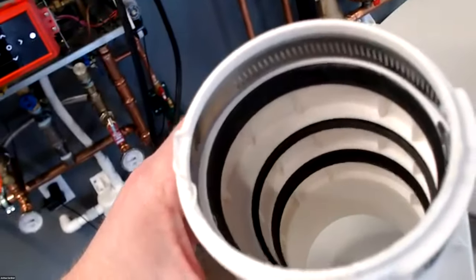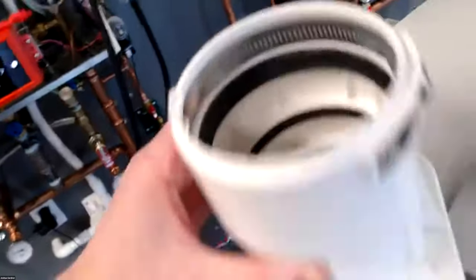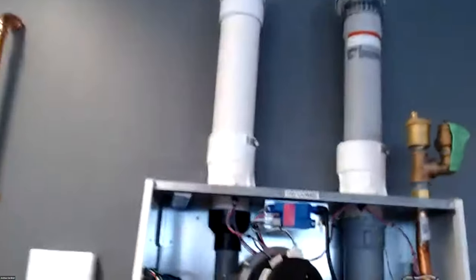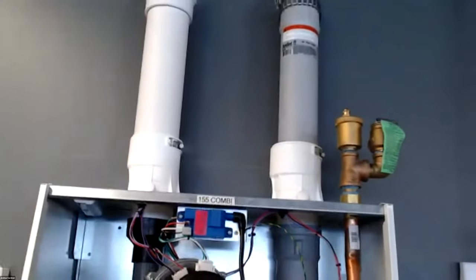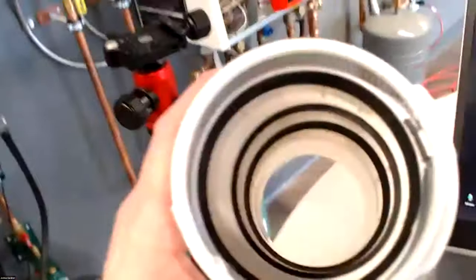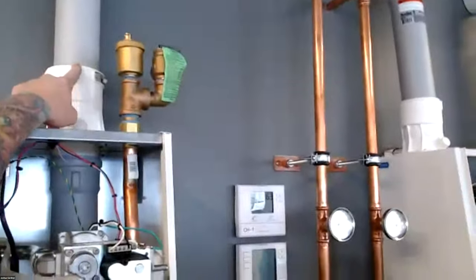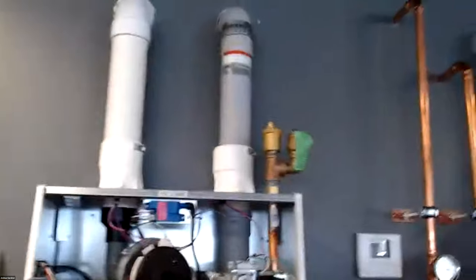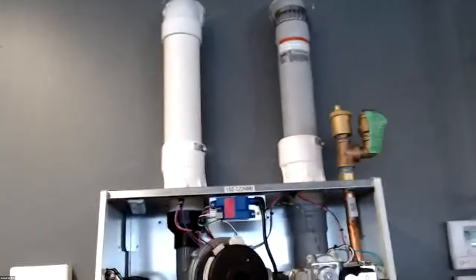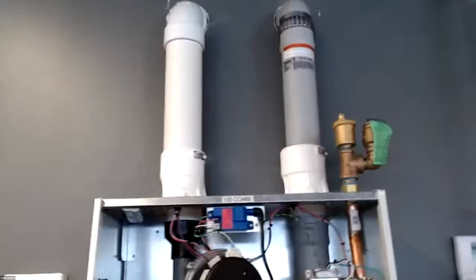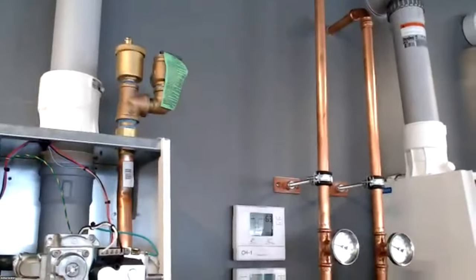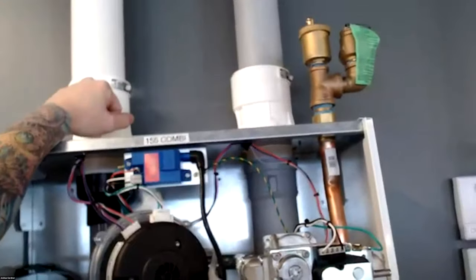So this boiler, right out of the box, can handle 3-inch PVC, CPVC, and poly, so DuraVent or Centrotherm, whatever you guys prefer using. And we have that step down gasket system, so we do not need vent adapters if we're using the poly system. On the 110s, we can run 2-inch PVC up to 28 feet, but with that, you will need a piece of 3-inch PVC and a reducing coupling and reduce it down. I don't recommend 2-inch just because I've seen issues with it.